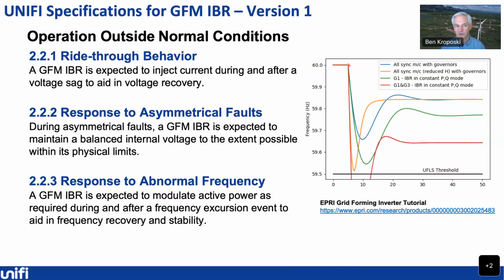What we're able to do with very fast grid forming and even some of the grid following inverters is actually arrest that behavior by injecting power and create a more stable situation. I'll put another plug in here if you're interested in much more detail on grid forming technologies. There's a great EPRI grid forming inverter tutorial that we have linked through our UNIFI website that you can find out a lot more information about. But in general, we want to make sure that they have proper ride-through behavior, proper response to asymmetrical faults, and also response to abnormal frequencies.